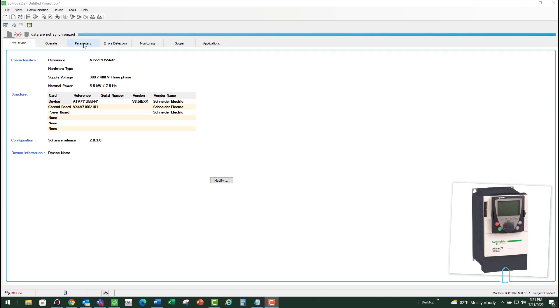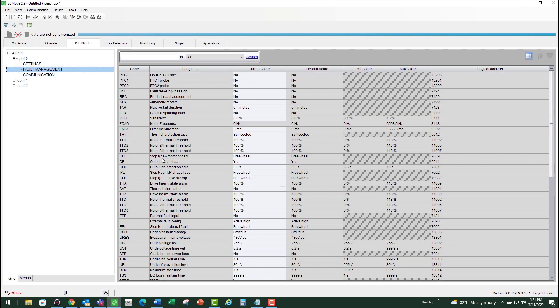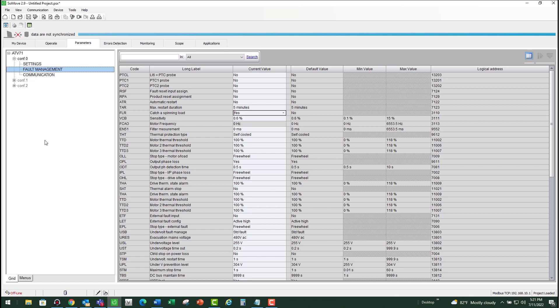I'll show you where the parameter is located using SoMove software. If you open the file and go into parameters, go under fault management and there you will see the FLR parameter which is right here. Make sure you turn that on, and of course you've got to make sure that your application allows it.